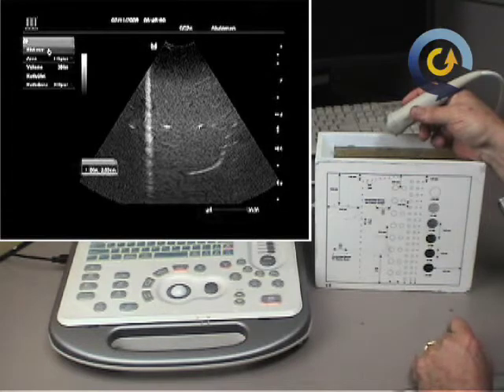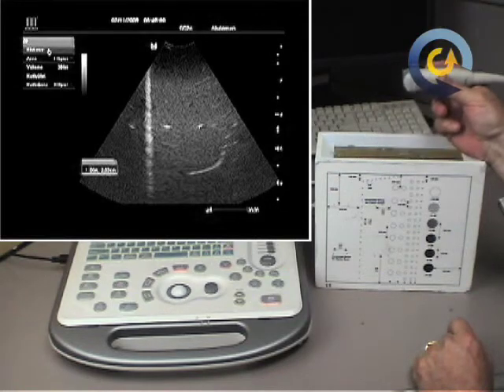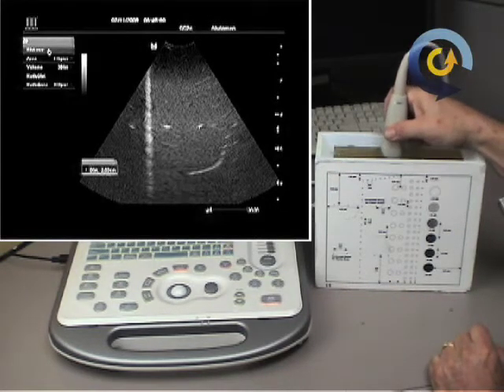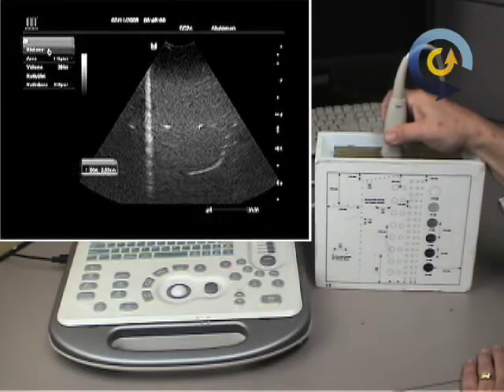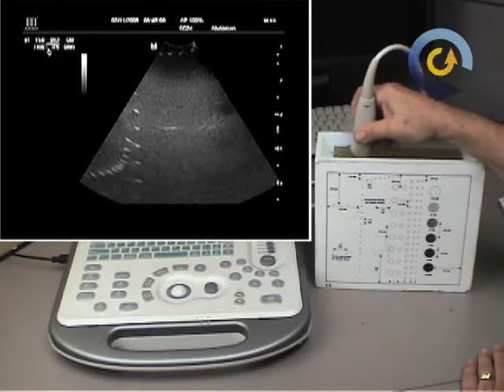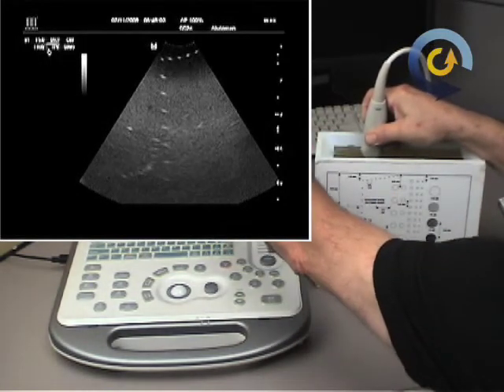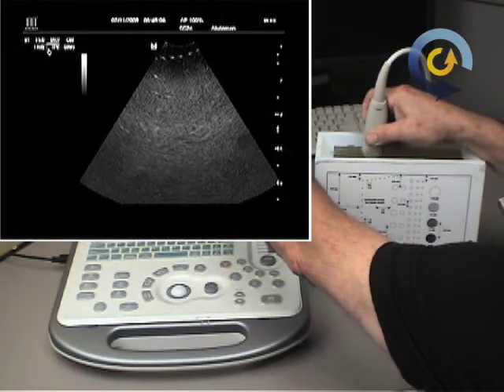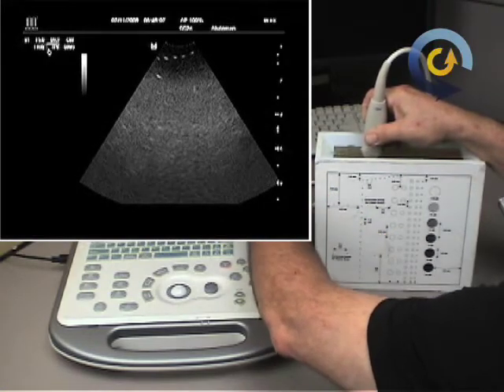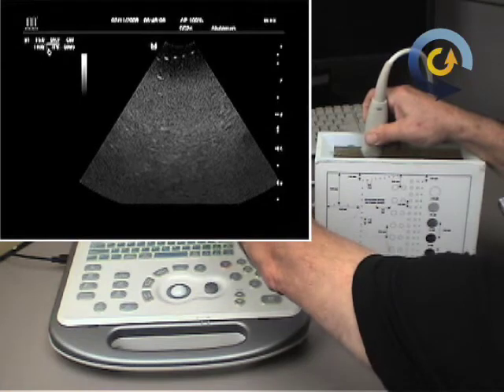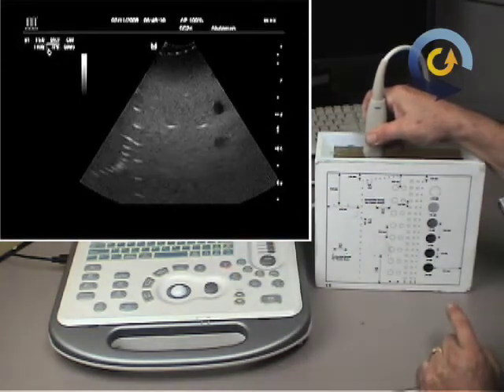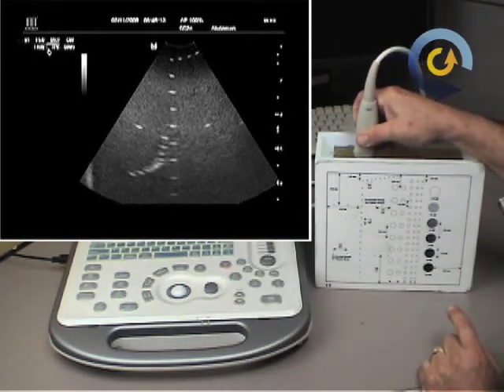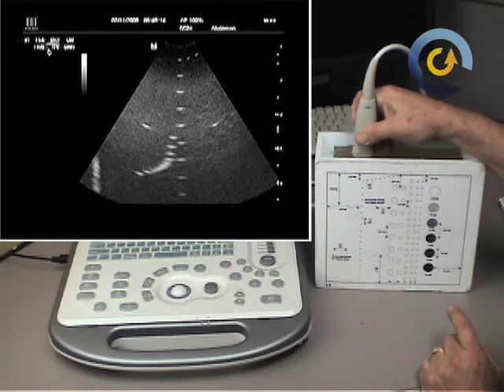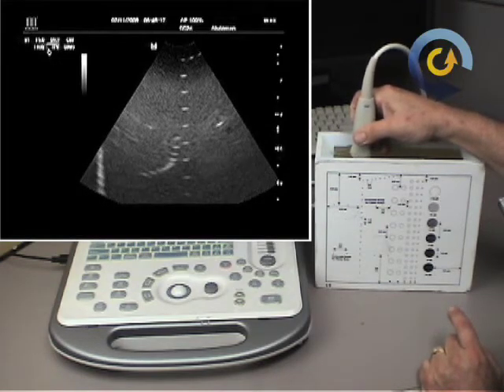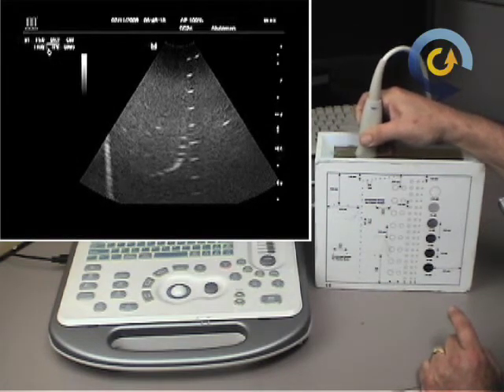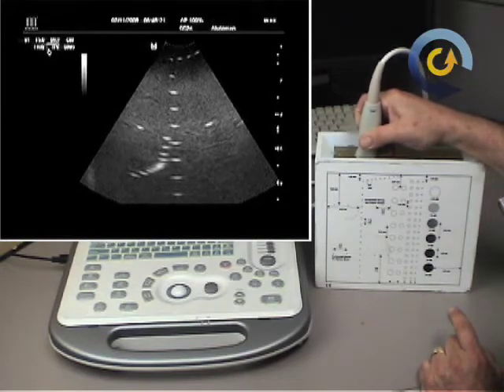You could easily put another transducer on, the same type of probe, same imaging setup, scan the phantom, and you'd readily be able to tell if that was your transducer that was at issue or not. Looking in the near field, I don't have that burned bright like you would on some probes, especially deeper probes. This high frequency probe has a nice clear near field on there. When you're doing something like looking for a breast cyst to find out if you're going to do a biopsy or not, that's what you want to be able to see, is a nice clear near field.